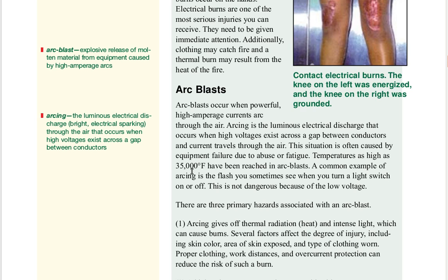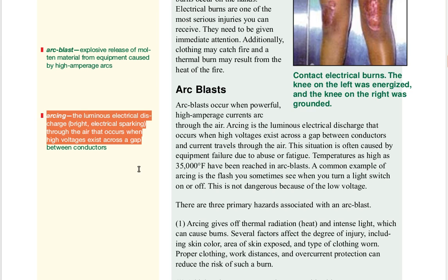Temperatures as high as 35,000 degrees Fahrenheit have been reached in an arc blast. Extremely hot, causing the metal to melt very quickly. A common example of arcing is the flash you sometimes see when you turn your light switch on and off. This is not dangerous because of the low voltage. When you're doing electric arc welding, you're making use of an electric arc, assuming that you are working safely. Arcing: the luminous electrical discharge, that means bright electrical sparking through the air, that occurs when high voltages exist across a gap between conductors.